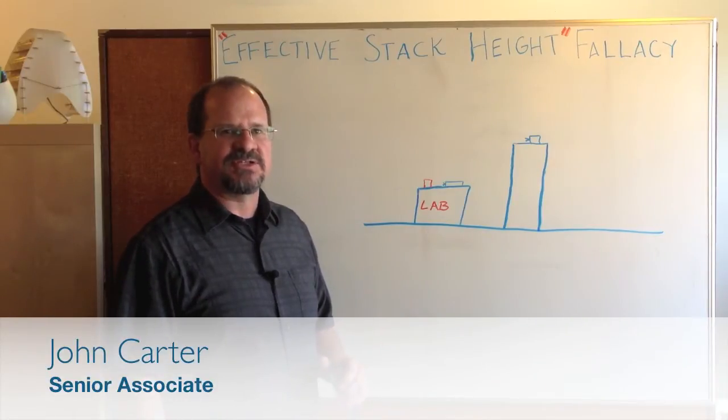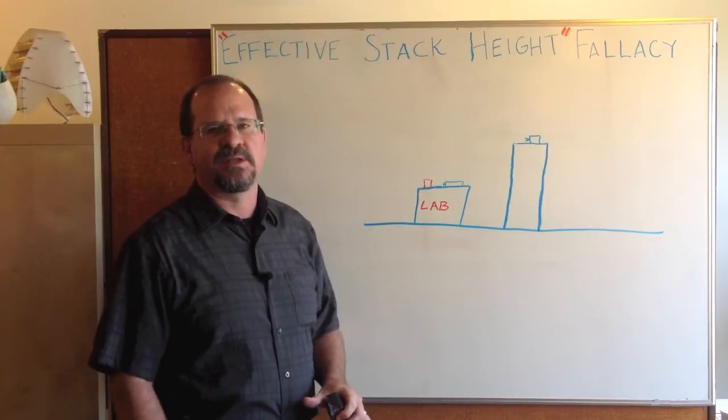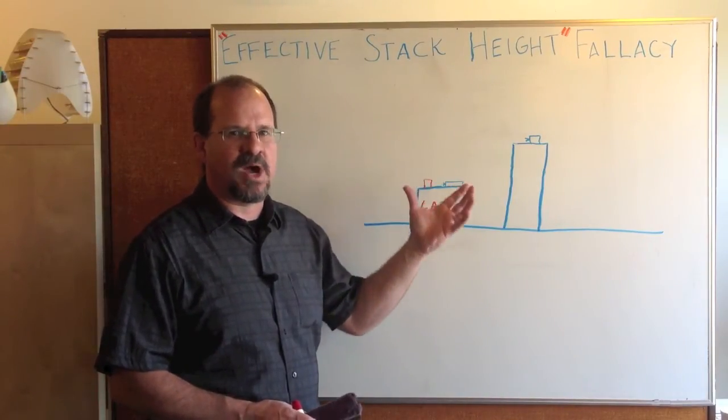When you're doing design for a laboratory exhaust system, one of the terms you could run across is effective stack height. That's not a real term for practical engineering design. I can show you where it came from and why not to use it.